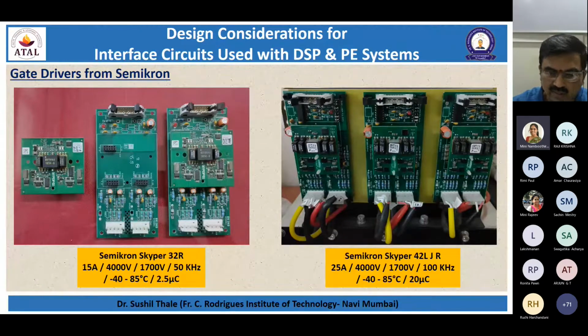Similarly, as we commonly discuss the capacitors used here, you can see in these devices the orange ones are the electrolytic capacitors, typically rated up to 85 degrees Celsius. There are ones rated higher available too, but most of them are 85 degrees Celsius. That means the major culprit in most designs turns out to be an electrolytic capacitor rated for 85 degrees Celsius that does not have sufficient ripple current capacity.